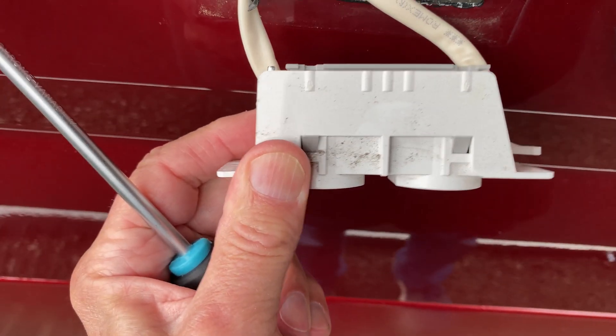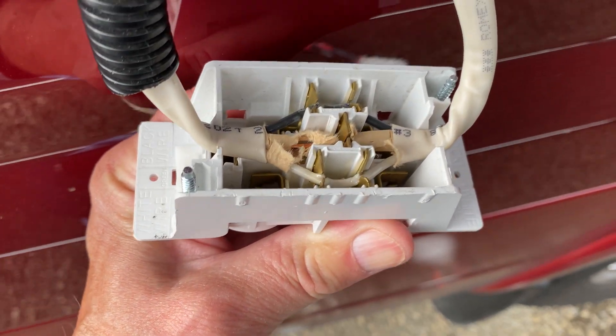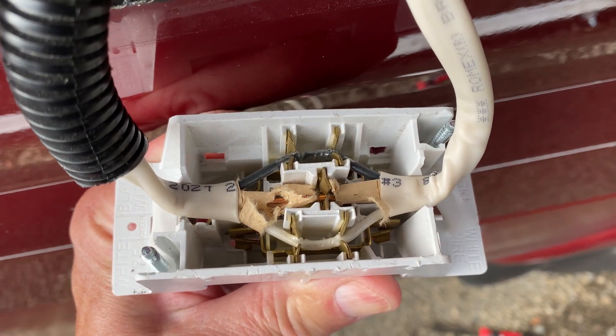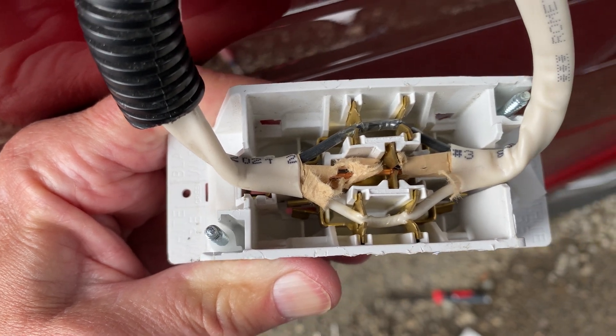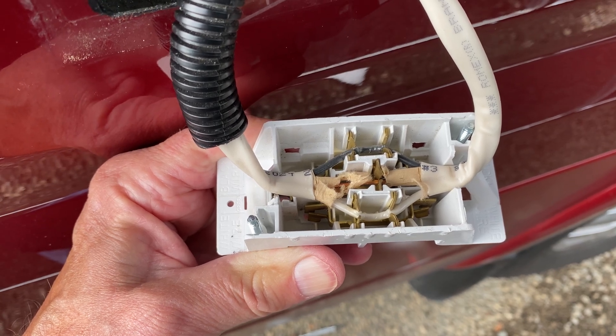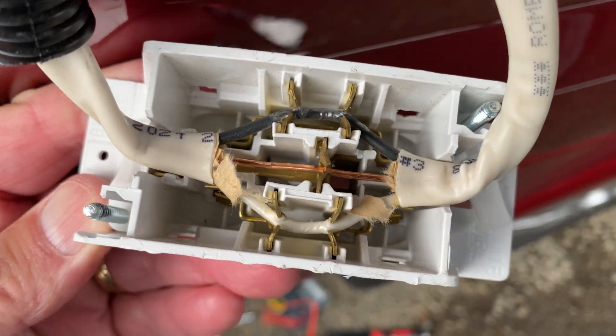With Diane's help, I finally got the back off this thing — I didn't record it because there would be some words I wouldn't want posted. I see no obvious visible issues here, but again we've got the paper on the ground wires and we're pinching the hot and neutral wires — who knows how good those connections are. I'll check continuity with my meter. Like the other receptacles, I removed the paper from around the copper ground. After struggling with opening up several of the plastic outlets, I realized this was too much of a job and gave up.